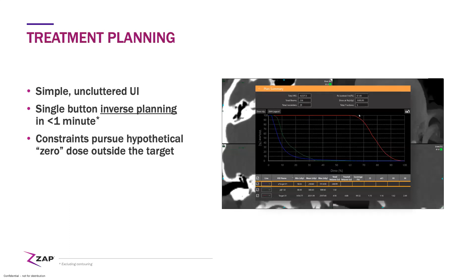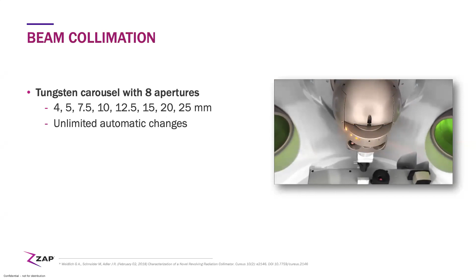Here's the collimation system again, with a little more detail. You see this spinning disc has a series of apertures ranging from 4 to 25 millimeters. In a second, we can change aperture sizes and deliver best-in-class dosimetry with the steepest possible dose gradient. And this goes on repeatedly, allowing us to optimize aperture dimension as one of the primary variables of treatment and achieving the sort of dosimetry I've been alluding to.